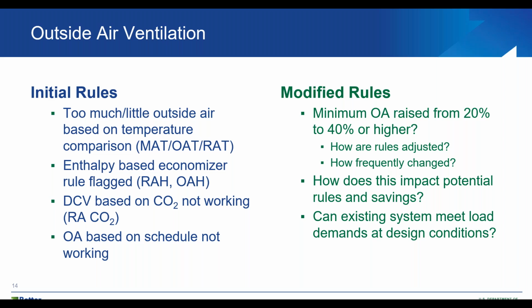Let's start with the first one, outside air ventilation. Under FDD, there are a significant number of rules that are typically written for outside air ventilation based on ASHRAE conditions, doing comparisons with temperature. Some people control economizers based on enthalpy, DCVs usually based on CO2, and outside air could also be based on schedule. So there are a lot of initial rules that have been written and currently working based on that.